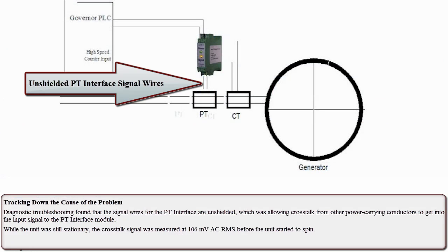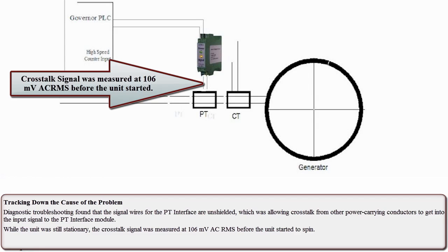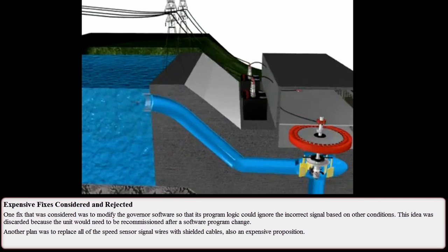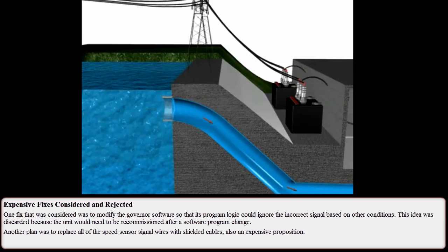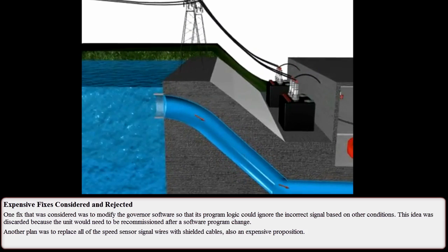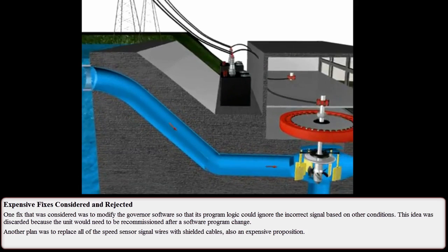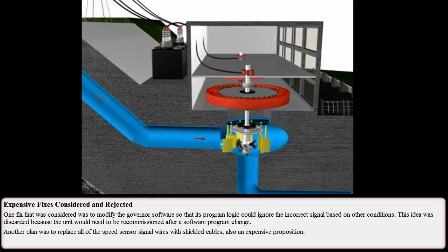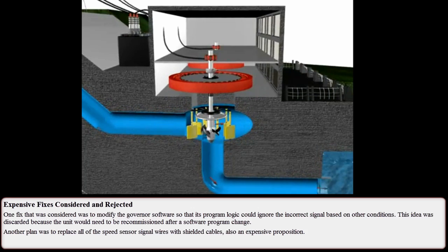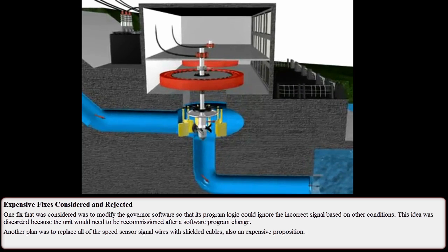Diagnostic troubleshooting found that the signal wires for the PT interface are unshielded, which was allowing crosstalk from other power-carrying conductors to get into the input signal of the PT interface module. While the unit was still stationary, the crosstalk signal was measured at 106 millivolts ACRMS before the unit started to spin. One fix that was considered was to modify the governor software so that its program logic could ignore the incorrect signal based on other conditions. This idea was discarded because the unit would need to be recommissioned after a software program change. Another plan was to replace all of the speed sensor signal wires with shielded cables, also an expensive proposition.